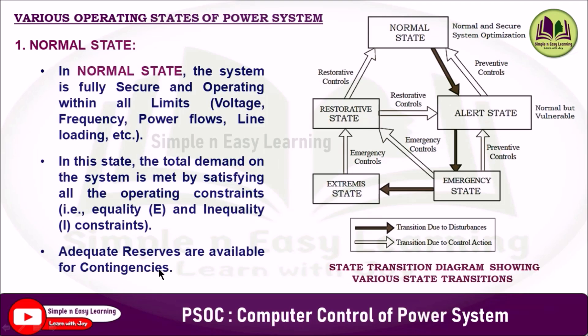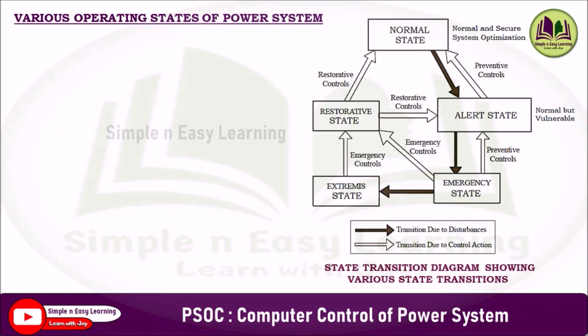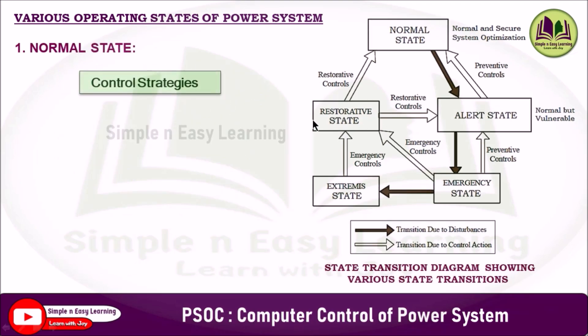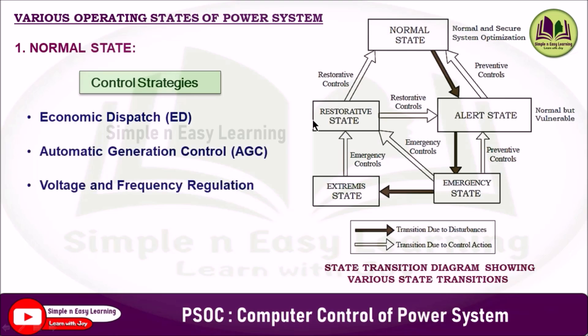Adequate reserves are available in normal state for contingencies. A contingency is an unexpected event or failure that affects normal system operation. Common types include generator outage (a power plant suddenly going offline), transmission line outage (a power line disconnected due to fault or maintenance), transformer failure, or a sudden increase or decrease in load. Control strategies in normal state include economic dispatch, automatic generation control, voltage and frequency regulation, optimal power flow, reserve management, and balancing.